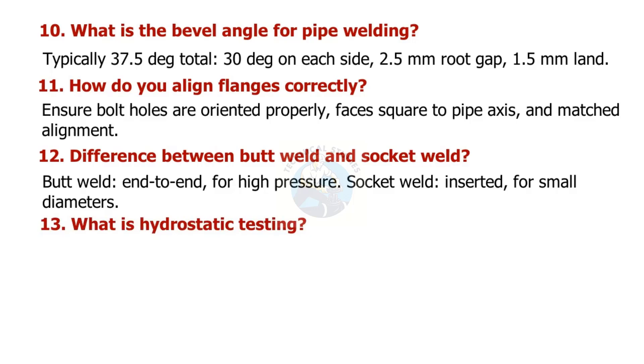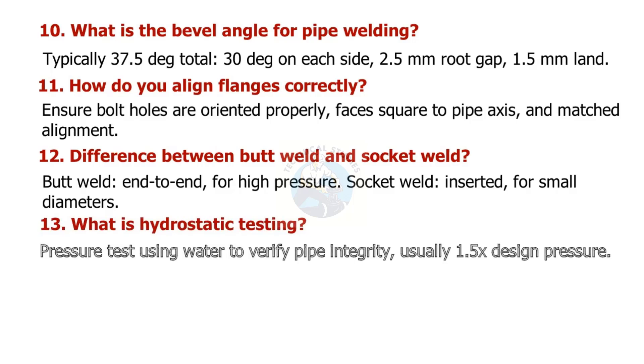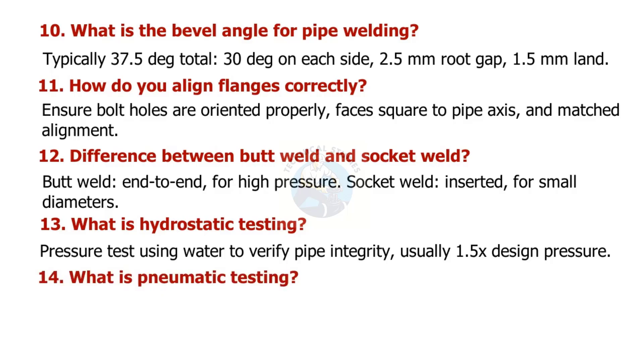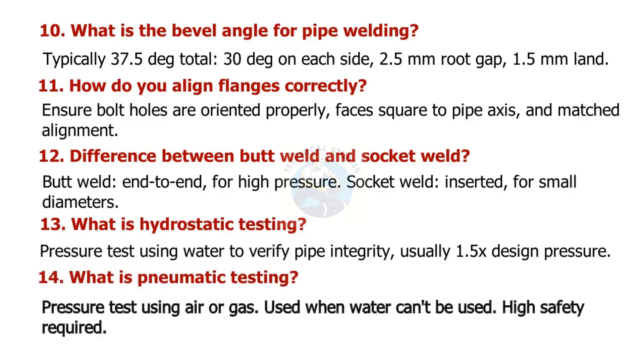What is hydrostatic testing? It is a pressure test using water to verify pipe integrity, usually at 1.5 times the design pressure. What is pneumatic testing? It is a pressure test using air or gas, used when water can't be used and high safety is required.